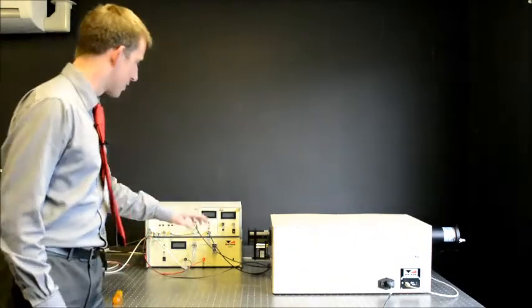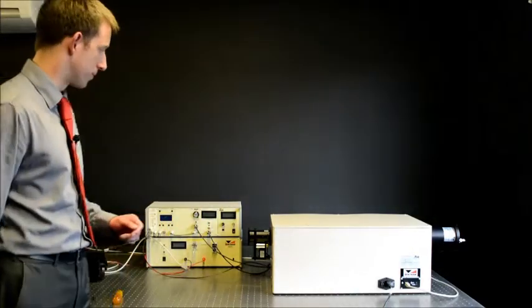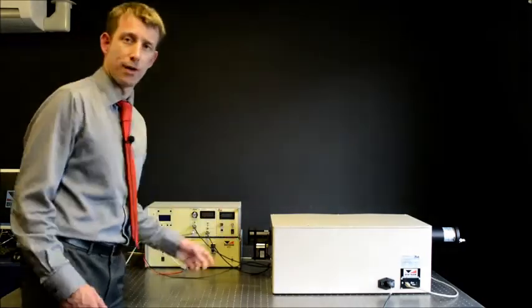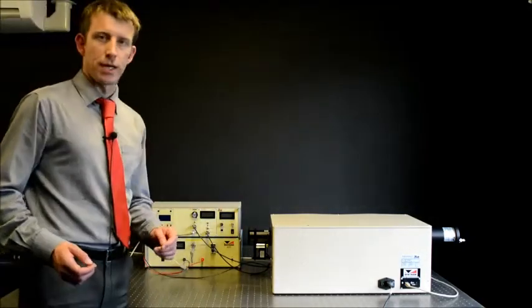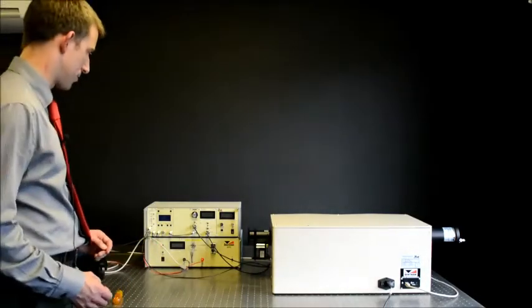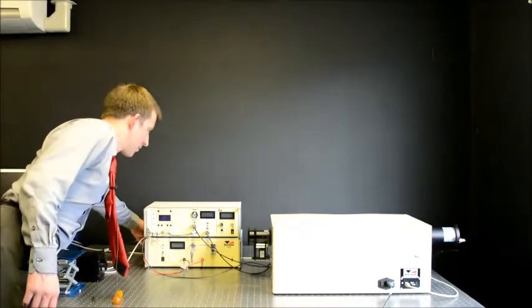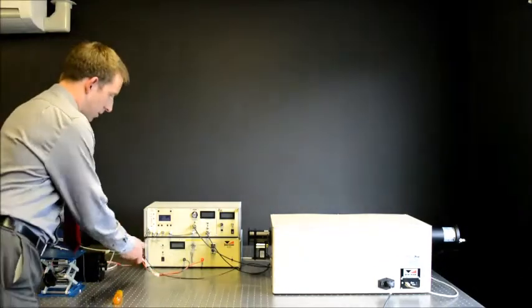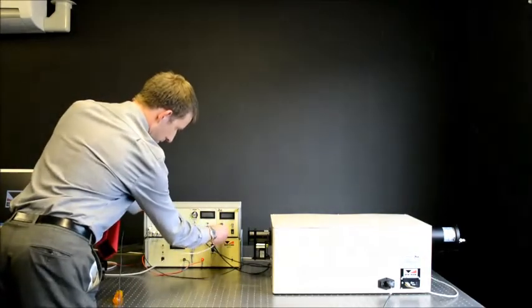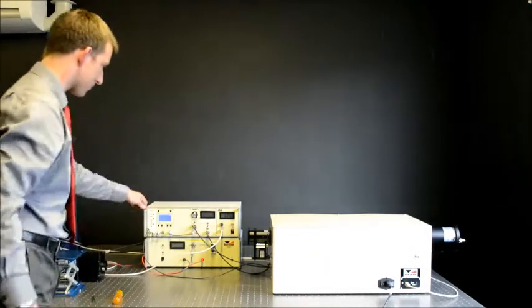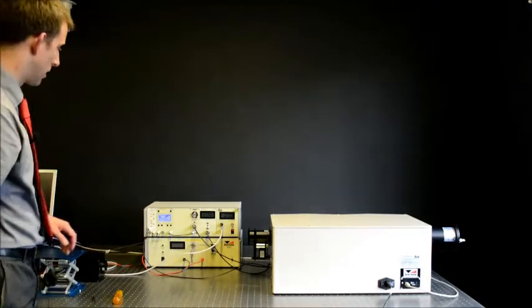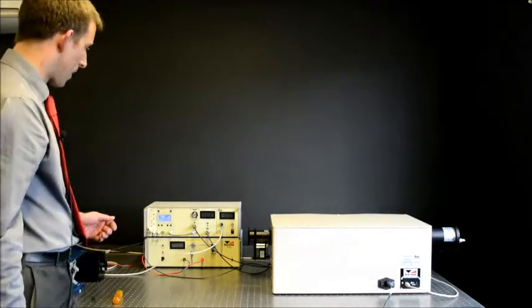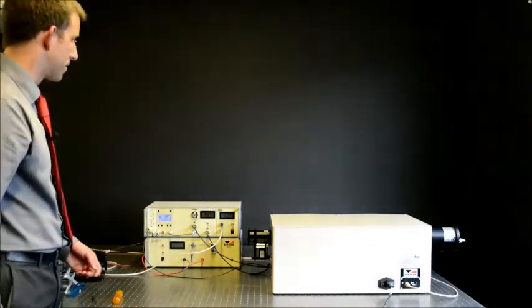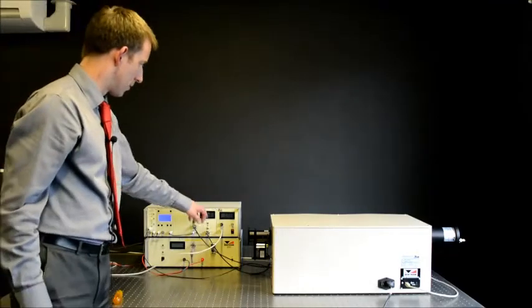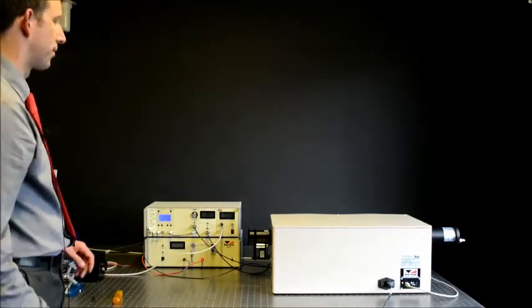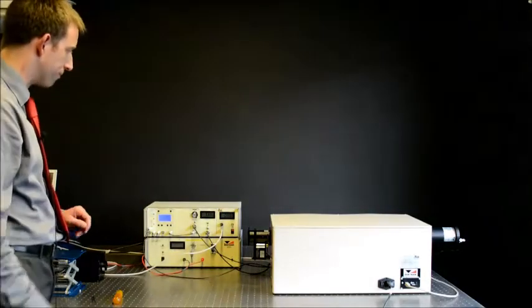The detector is cooled using the CPS-1M module. This is set to half an amp in the factory, which will obtain around -10 degrees device temperature. I've powered on the mains of the 417, and we can connect the USB and power on the unit. The 496 lock-in amplifier will boot, and with the CPS-1M toggled to the on position, it will gradually settle at 0.5 of an amp. This will vary with the ambient temperature in the room.